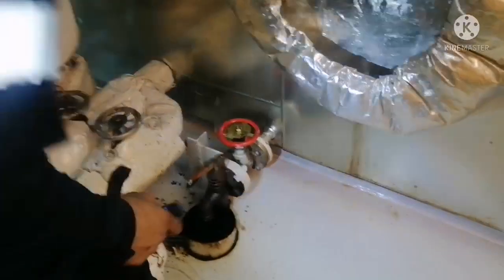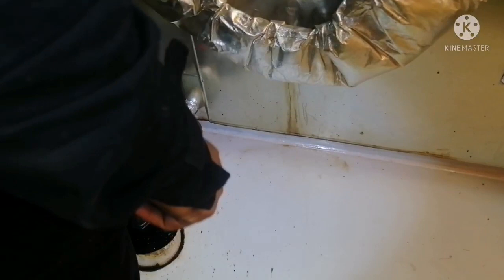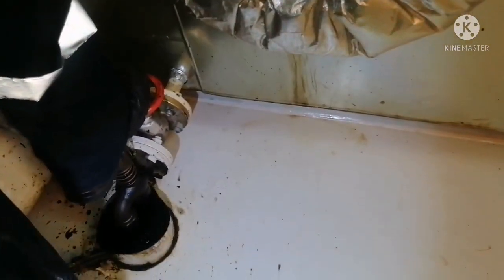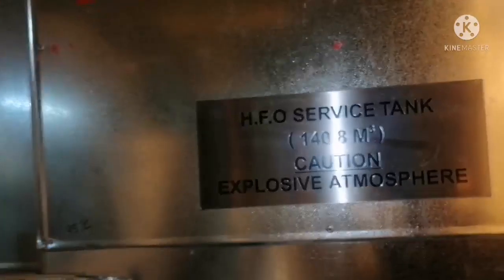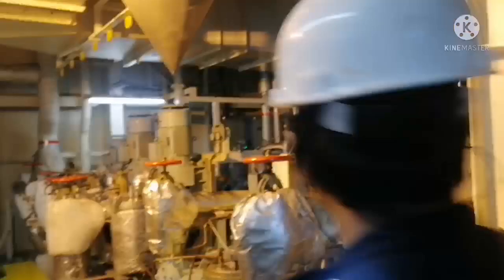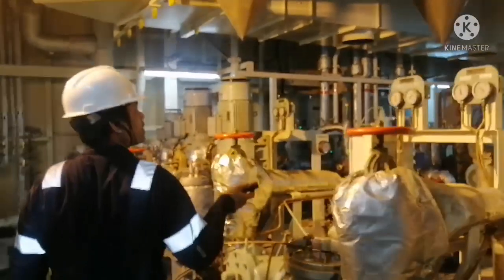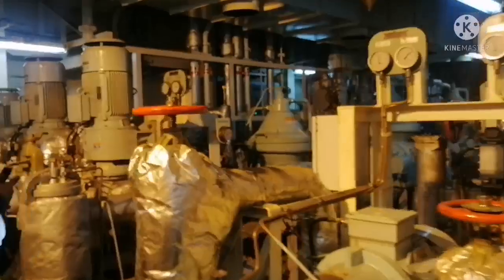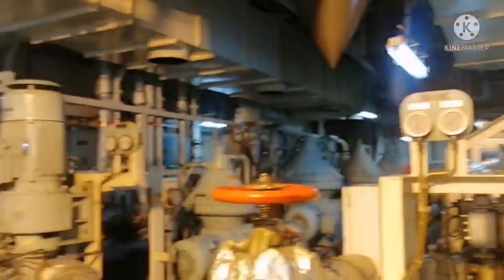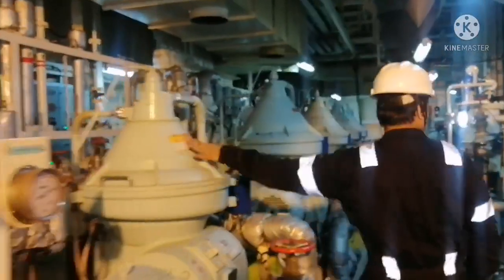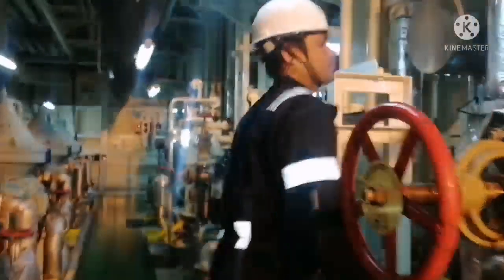Another pipe. Just open the valve and press the spring. You can find the water mixed with the oil will come out. Once you find the oil is only coming, then you can stop draining the oil. So this is your fuel oil circulating pump, main engine fuel oil circulating pump, service pump. All purifiers will be here.